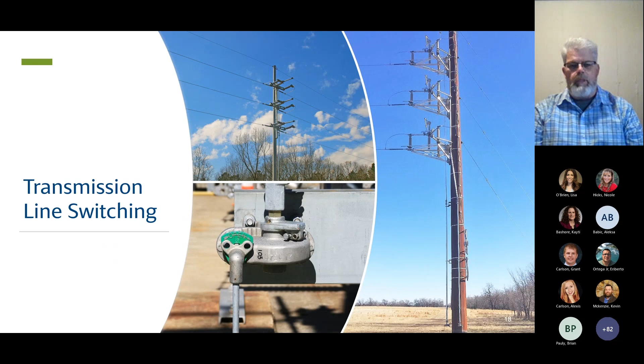So if you're required to switch on a pole switch - and I know all our linemen are highly qualified and know what they're doing - just think for a moment: what do I expect to hear when that switch operates? What do I expect to see above my head? How long is that line I'm about to de-energize? Can the switch handle it? If there are whiskers on top of the switch, are they in place and still connected? So pole switching could be challenging.